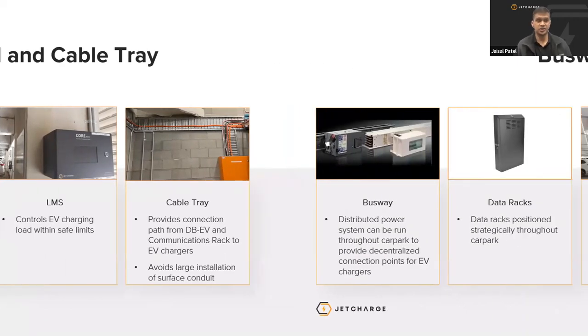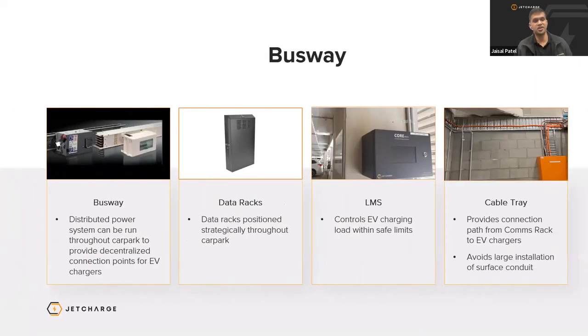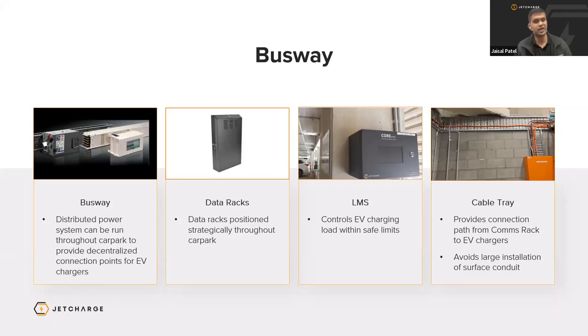With busways, we can essentially run a distributed power system throughout the car park to provide a decentralized connection point for EV charging. So each circuit runs back to the busway, but does not have to go to a centralized distribution board. There is essentially a tee-off unit with a circuit breaker in it that provides circuit protection to the charger. The whole bus is electrified, which allows for modular installations of EV chargers.